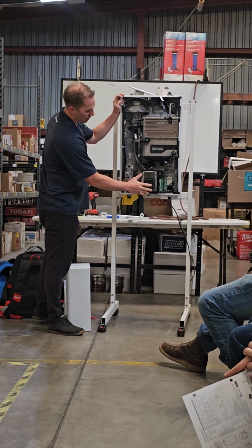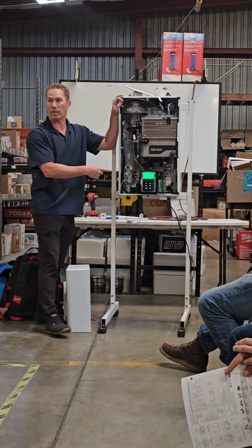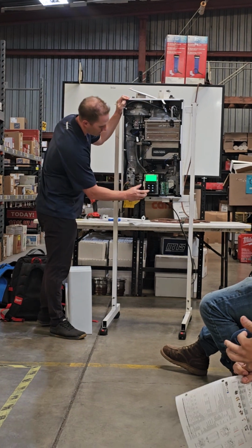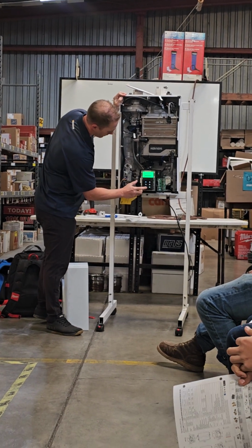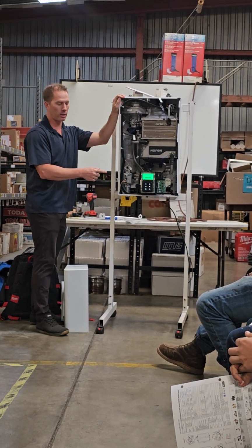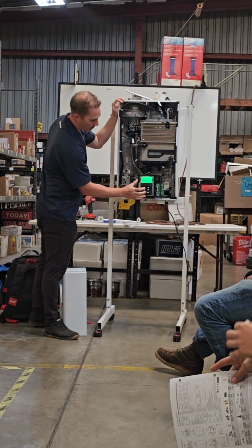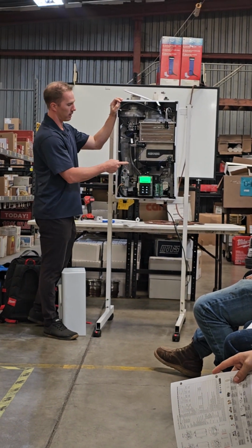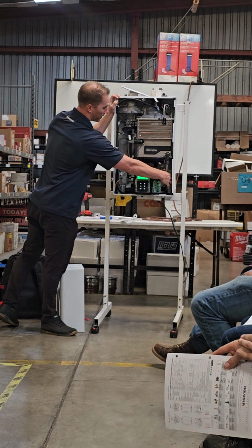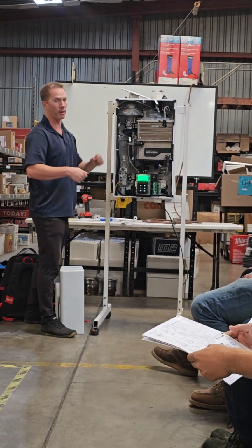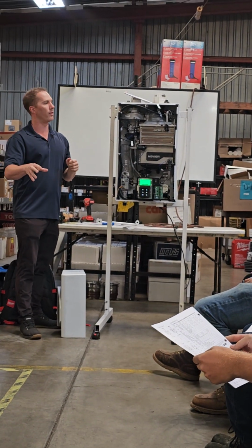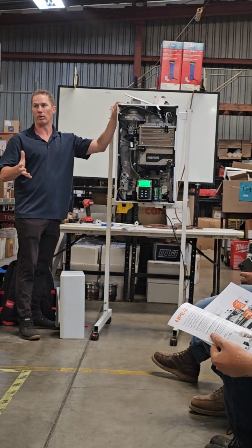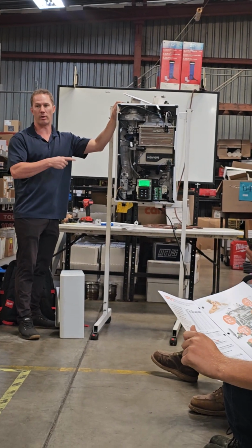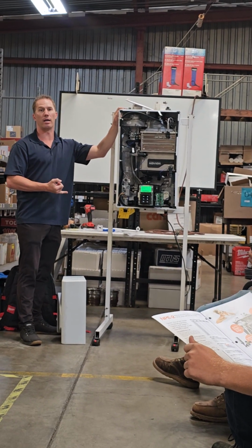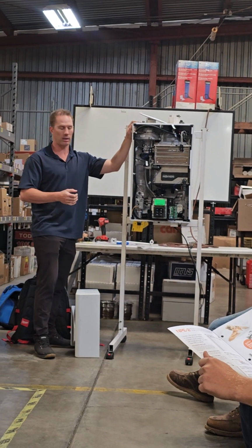So it's going to prompt you again to remind you not to forget about the two-way valve. Then it asks, is there an external pump? We're going to say no, because we're using an internal pump. It asks that question because it will power up a piece of the PCB board where you plug the external pump cable in, and then the Navien unit can actually control an exterior pump with its timer, so you don't have to buy a separate timer or aquastat.